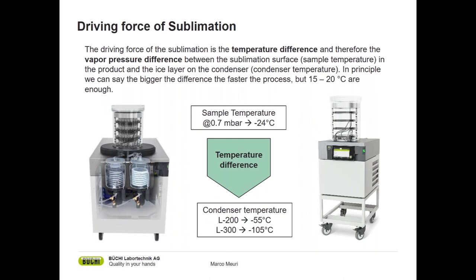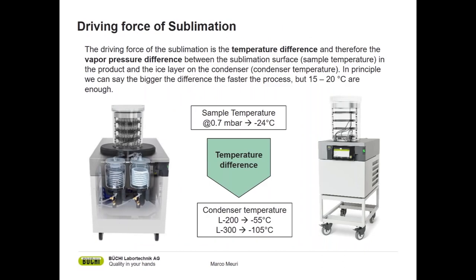A very common misunderstanding in freeze drying — going back to this table — is that the lower the pressure, the faster the freeze drying process will be. This is not correct, because the lower we set the pressure, the lower the sample temperature will be, down to minus 50 or minus 60 degrees. This would reduce the temperature difference, making the process much slower. That's why we choose typical pressures between one millibar down to about 0.1 millibar, depending on the melting point of the sample.